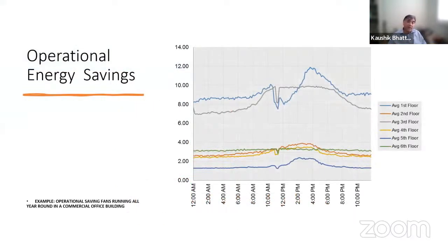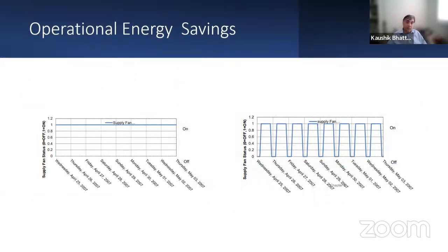Another common measure, as I said earlier, is scheduling. This is a building where you find that all the floors had compartmental fans on each of the floors, and these fans were running 24/7, even when the office was unoccupied. So there was an opportunity to turn off the equipment during the after hours. And again, here is another example of a supply fan running 24/7 versus actually scheduling.